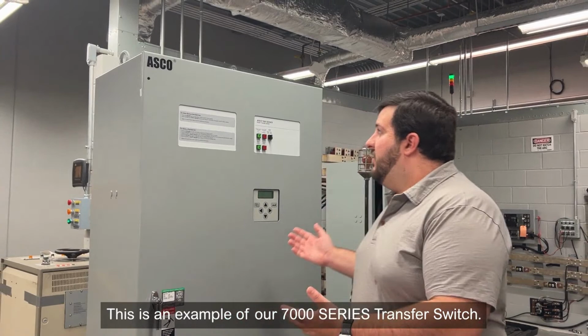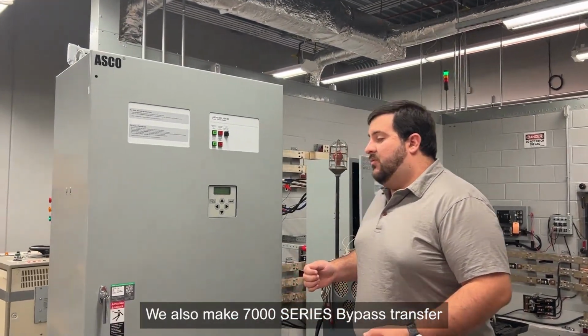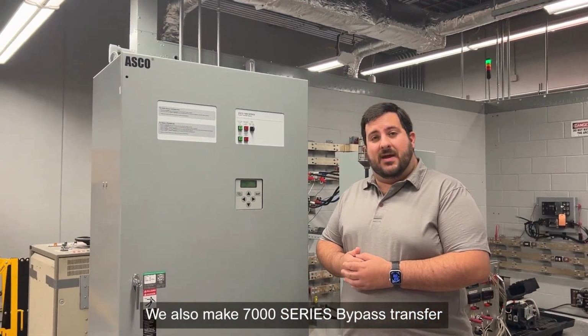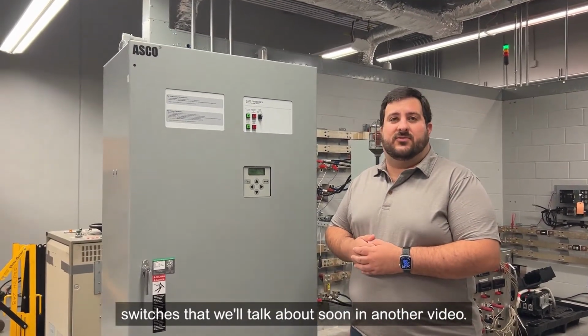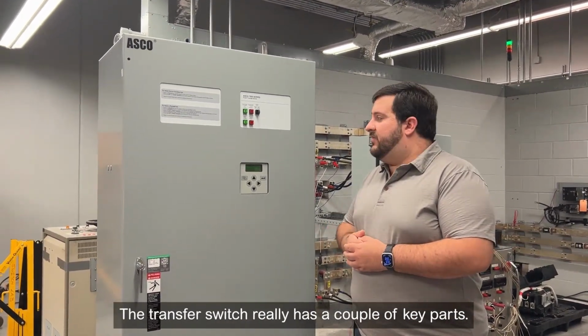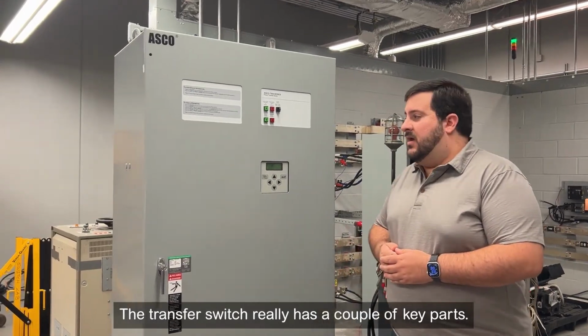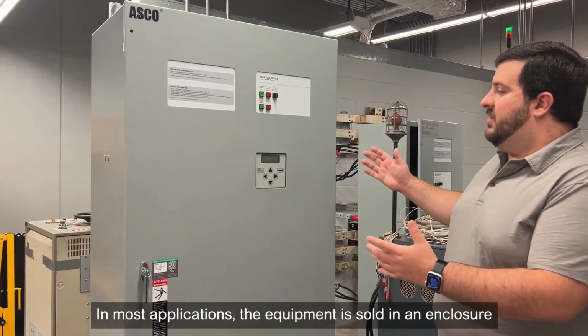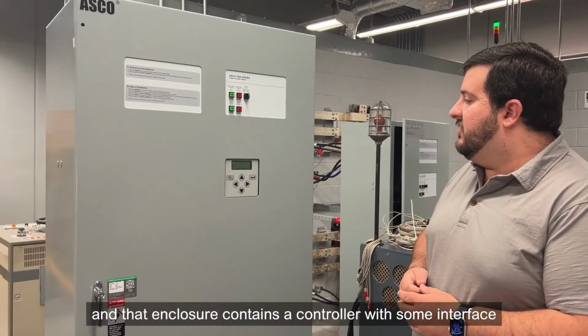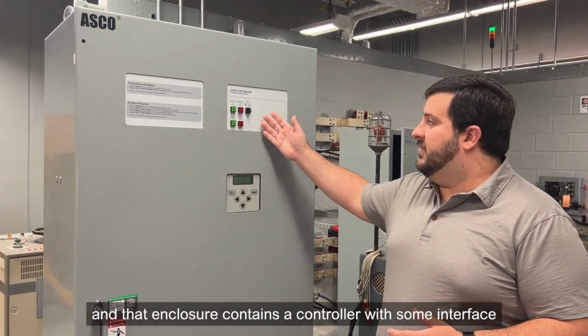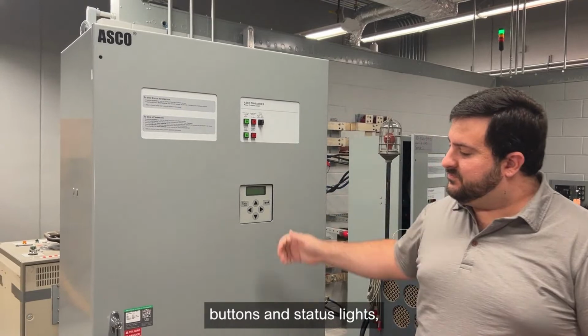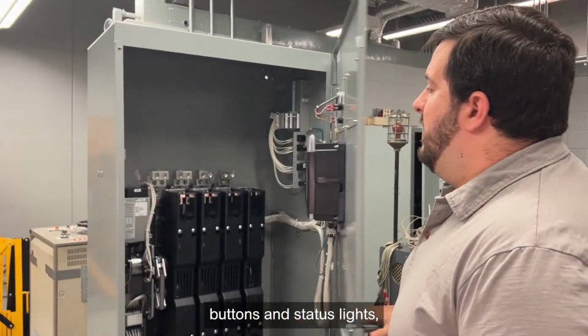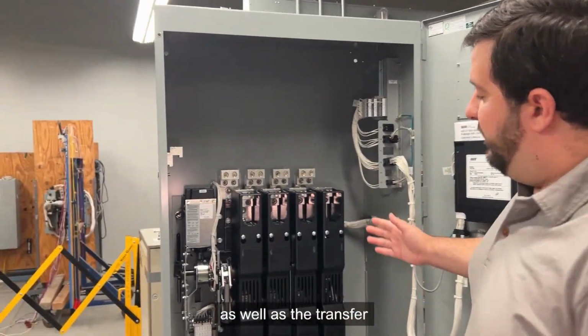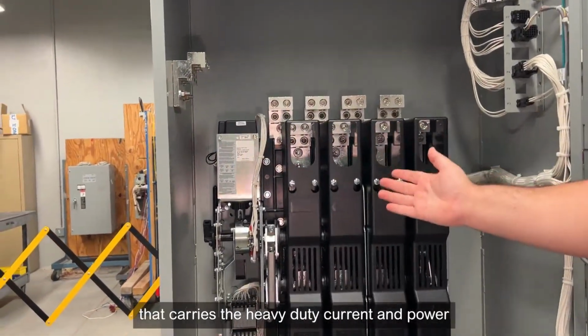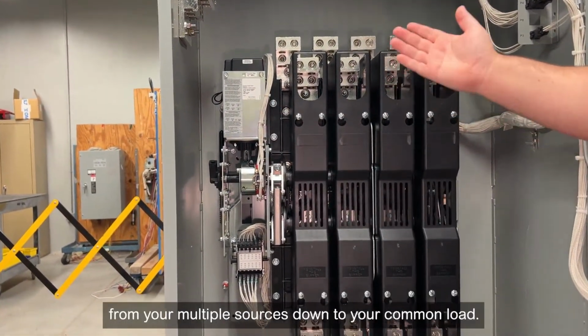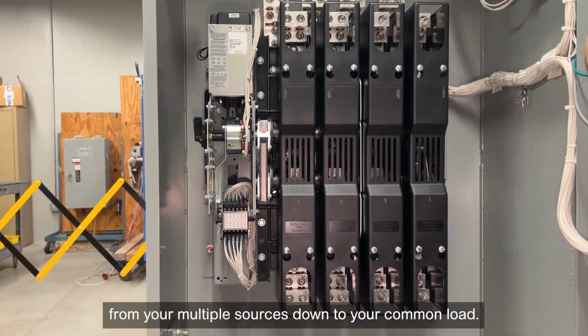This is an example of our 7000 series transfer switch. We also make 7000 series bypass transfer switches that we'll talk about soon in another video. The transfer switch really has a couple of key parts. In most applications, the equipment is sold in an enclosure, and that enclosure contains a controller with some interface buttons and status lights, as well as the transfer switch itself, which is the device that carries the heavy-duty current and power from your multiple sources down to your common load.